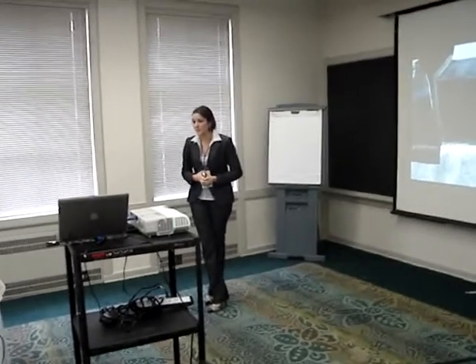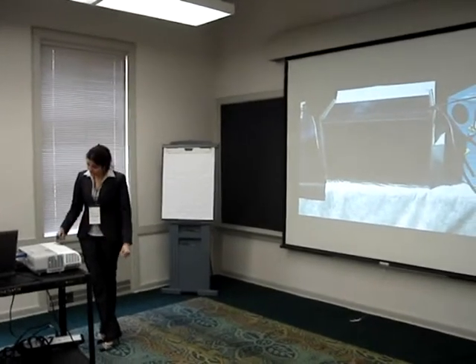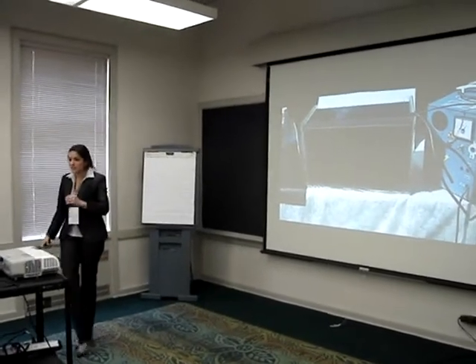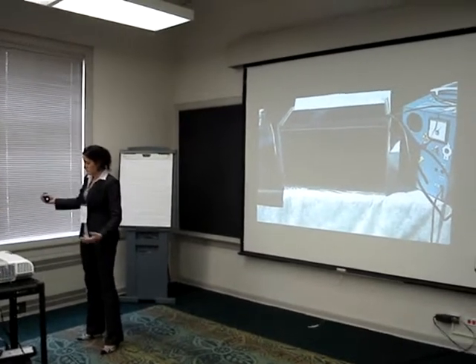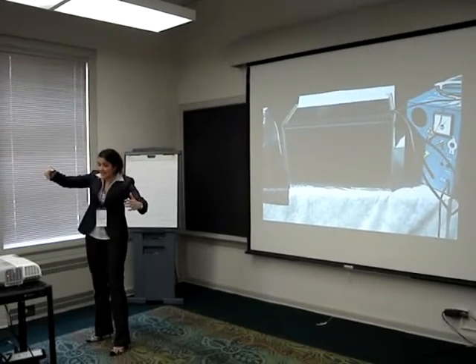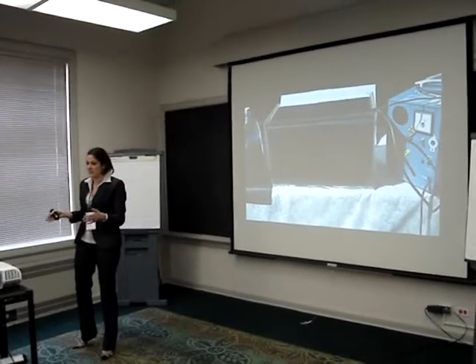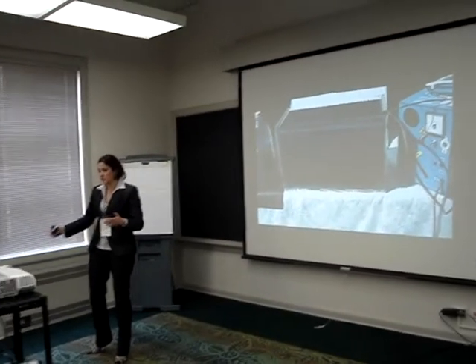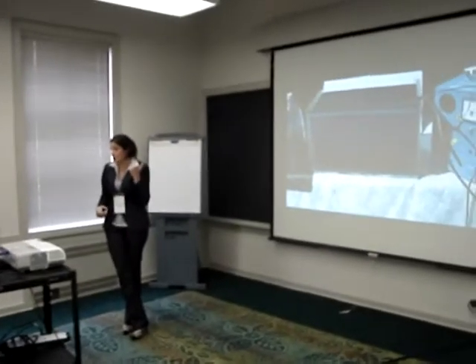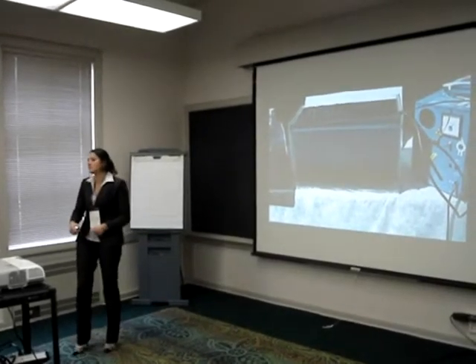And hydraulic detention time means you fill up some tank and you wait. Exactly. Something is happening while you're waiting, but it's not a continuous process, it's a batch process. No, it's a continuous, but the water that comes in, the tank should be big enough so that it stays for the hydraulic detention time there, and it will only come out after the hydraulic detention time. It's a project parameter. Engineers use that. It's a flow, relative flow rate issue. Yeah. Got it, okay. It depends on the type of treatment. The physical-chemical treatment takes around 3 hours, okay, to coagulate, to decantate.